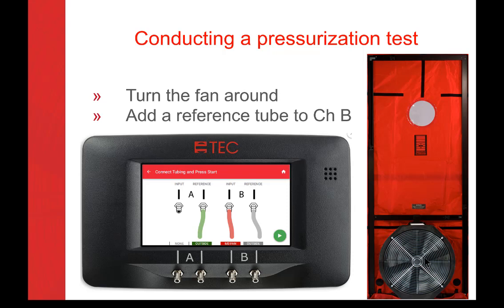And if you follow the tubing assistant and tell it that you're doing a pressurization test, it will tell you that you do need to have another tube going to the outside on channel B reference. Your kit came with a T connection that has two short pieces of tubing, so you could put those short pieces of tubing on reference A, reference B, and then the tube going to the outside.